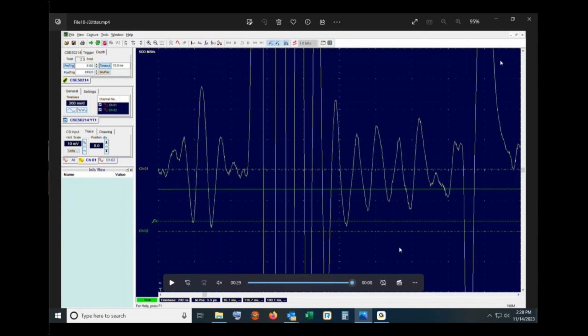And so each half of the range has half of the 256 levels across it, 128 levels. If you ignore the difference between 100 and 128, it turns out that this division height here is equal to 1 level on an 8-bit digitizer. So what that means is that if we were using an 8-bit digitizer, all of these subtle echoes here, the staircase would be 1 division high. So this one level high. So this echo, for example, which is about 2 divisions high, would show as two staircases, if you see what I mean.